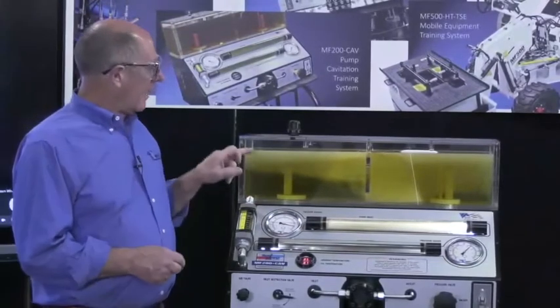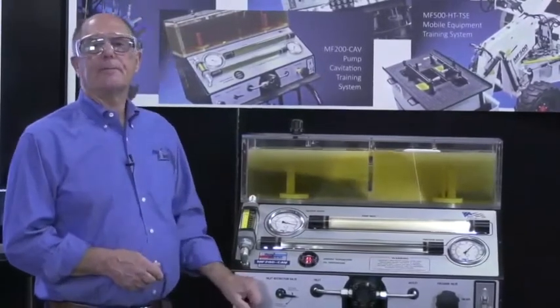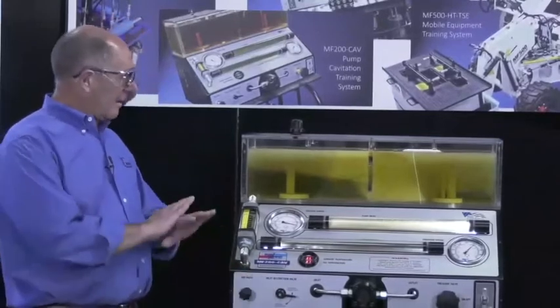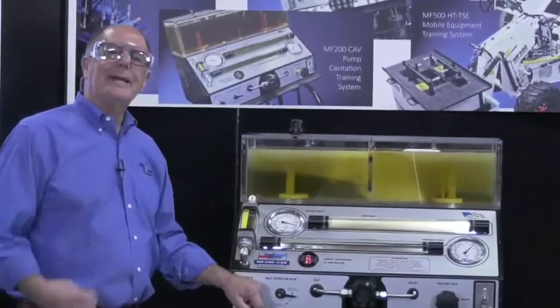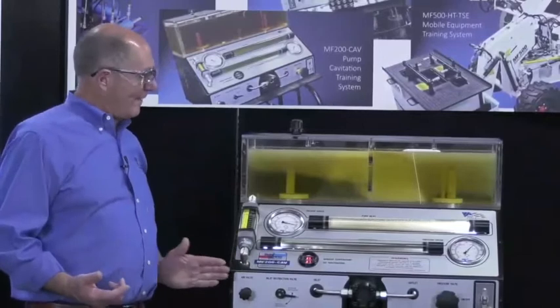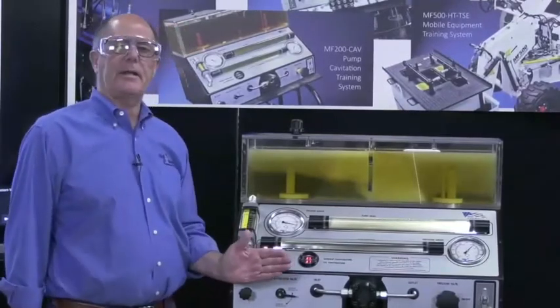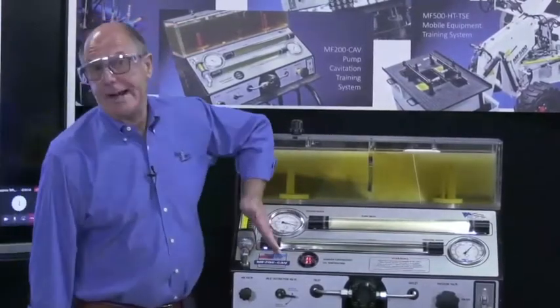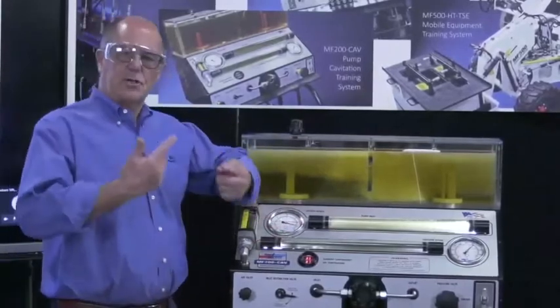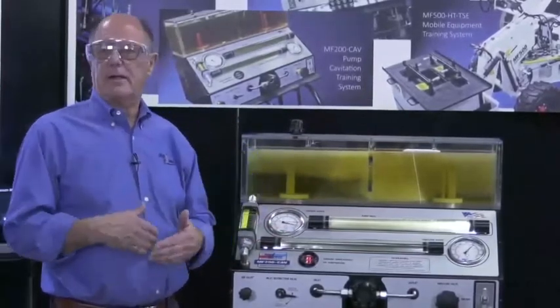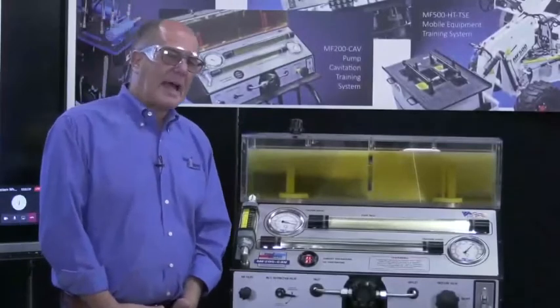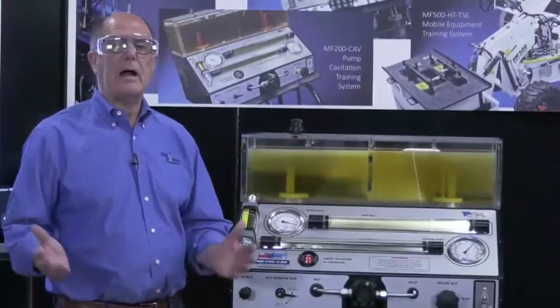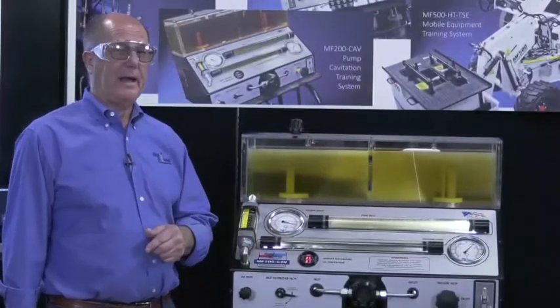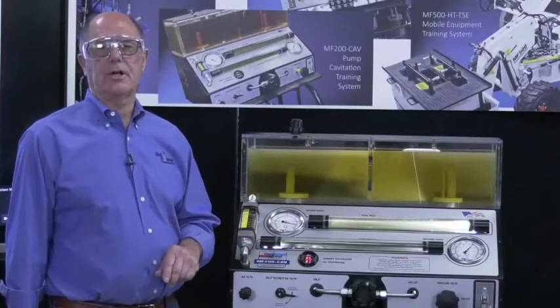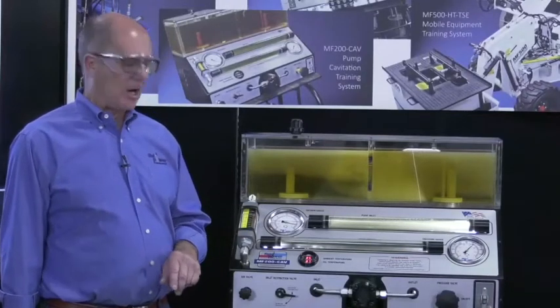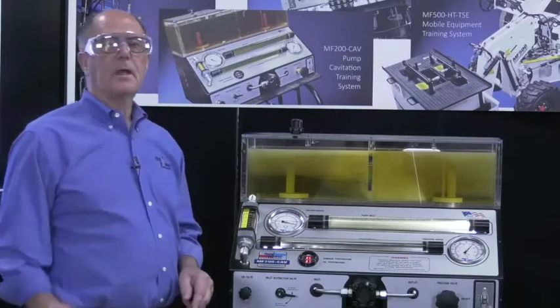Second, I went to aeration. Back to normal, I opened the air inlet valve and I fed just a small amount of air into the intake of the pump. Inlet restriction went down, and of course, as you saw, it started to perpetuate aeration, contaminated my oil and my entire hydraulic system with air. Terrible condition.